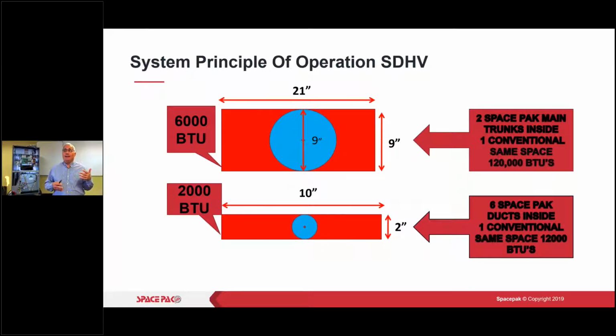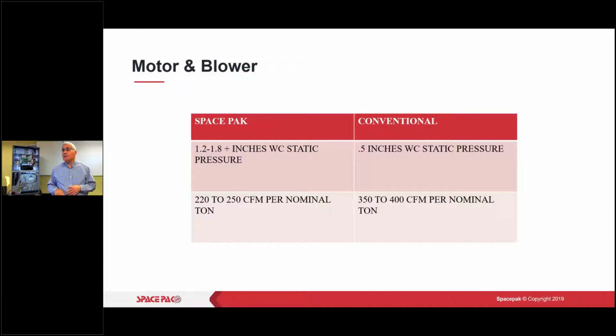And then on my 2-inch drops, I can replace a 10 by 2, and that's 2,000 BTUs. So the ability to run the plenum in many configurations, and then take your 2-inch drops off of that to get into your rooms below and/or above, makes SpacePak a good fit for you on a lot of retrofit jobs, but again, also new construction, so we don't take up as much space. The other difference with SpacePak is we are a high static system.